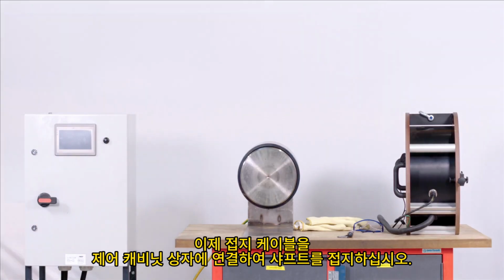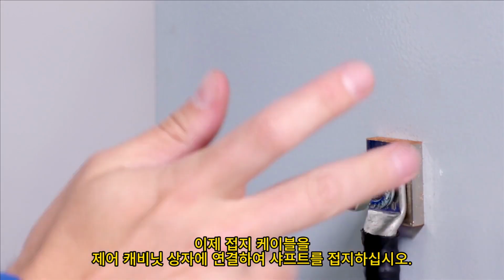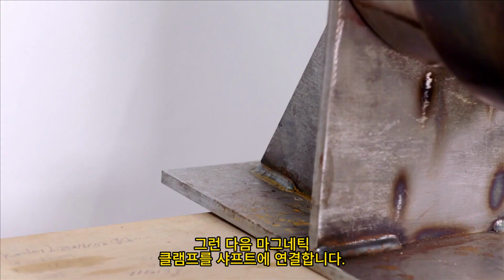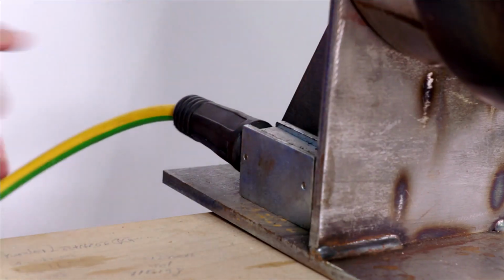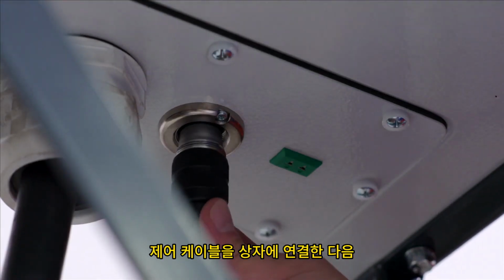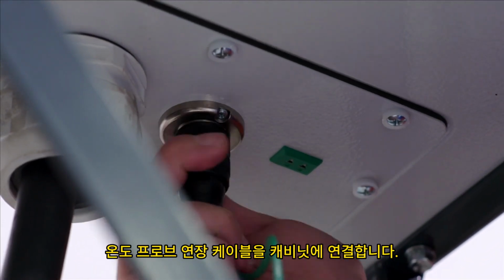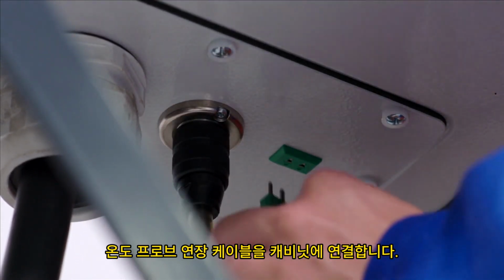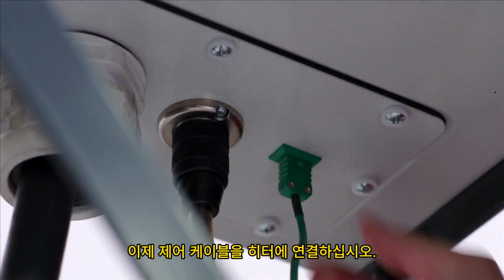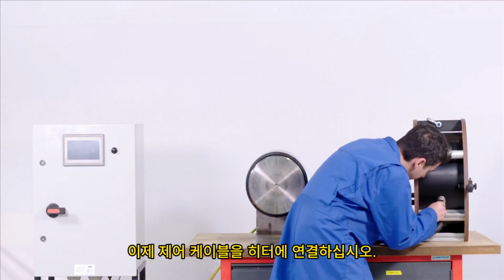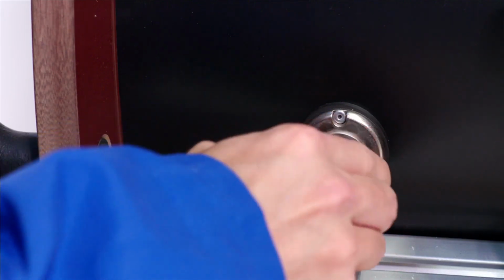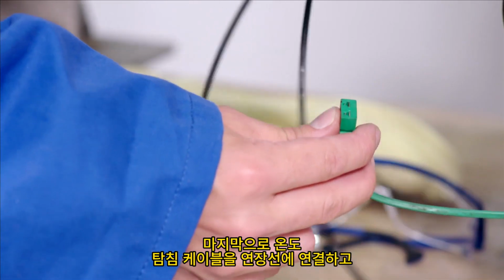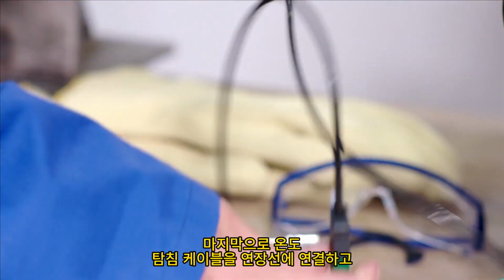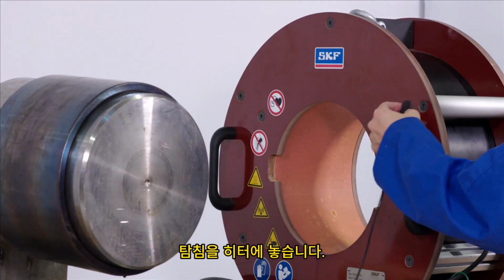Now earth the shaft by connecting the grounding cable to the control cabinet box. Then connect the magnetic clamp to the shaft. Connect the control cable to the box, and then the temperature probe extension cable to the cabinet. Now connect the control cable to the heater. Finally, connect the temperature probe cable to the extension and place the probe on the heater.